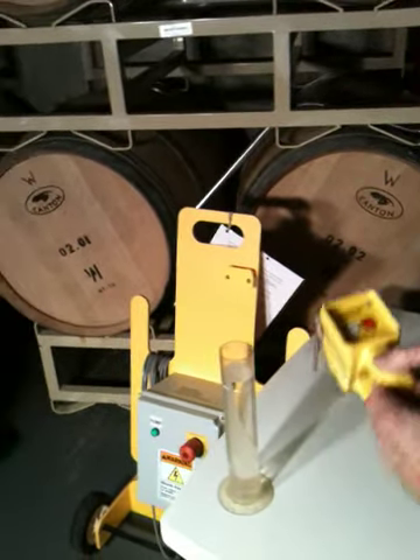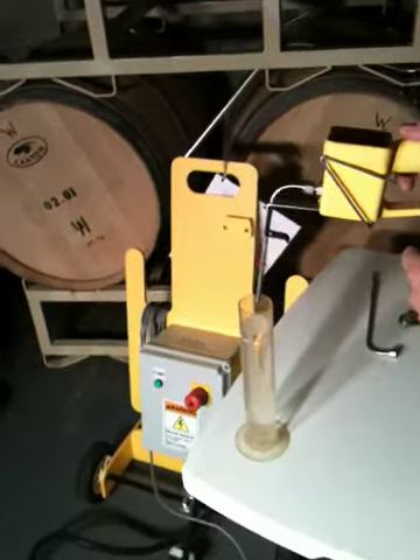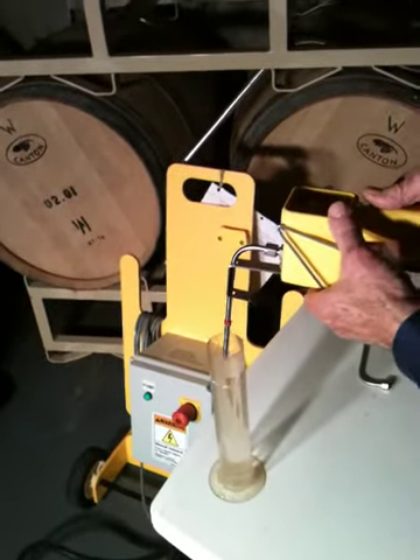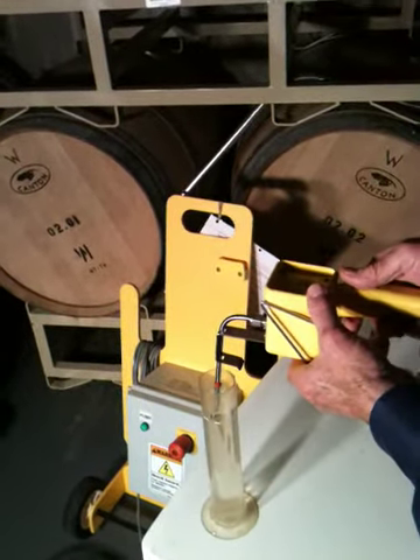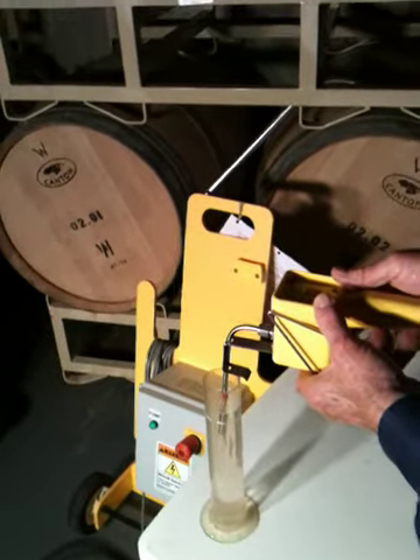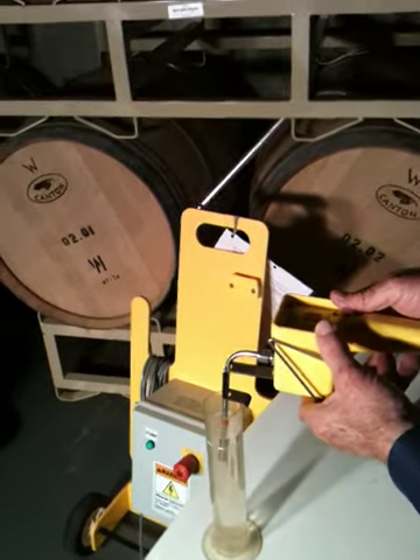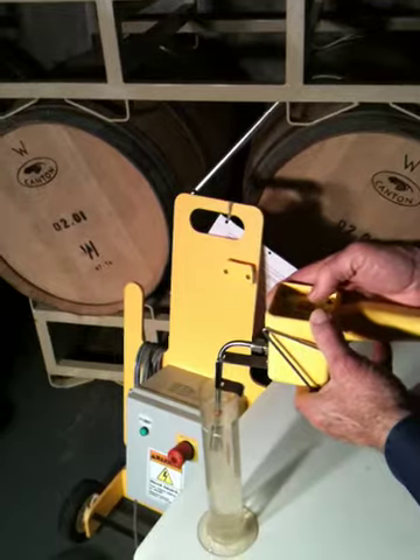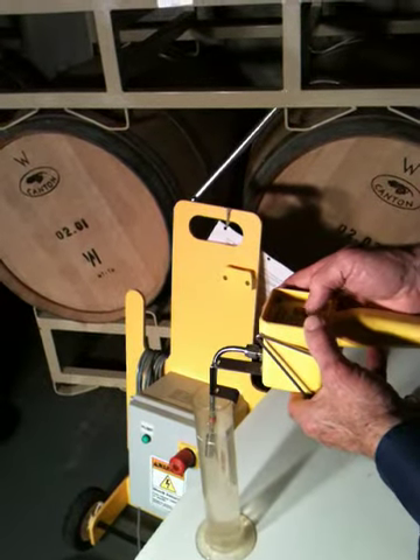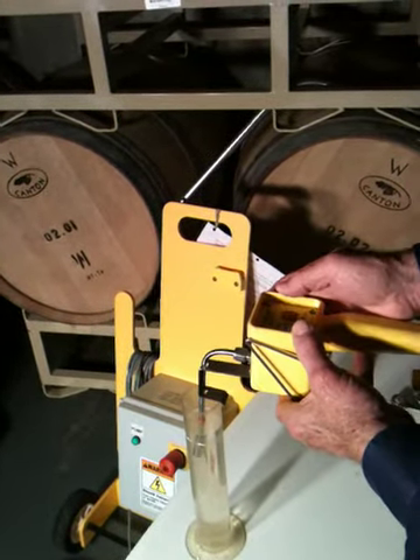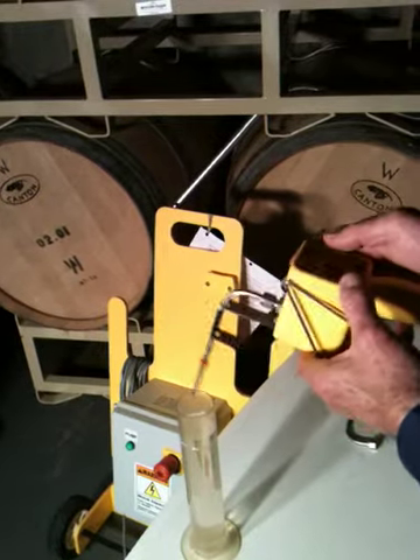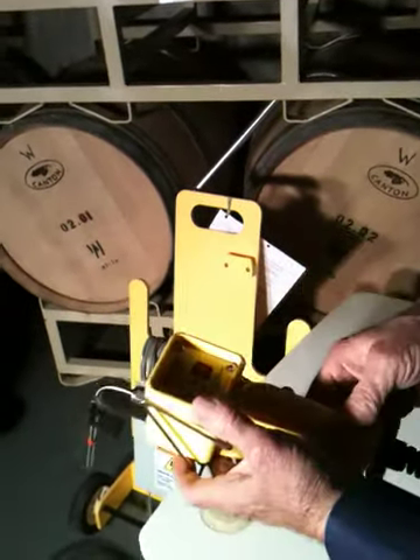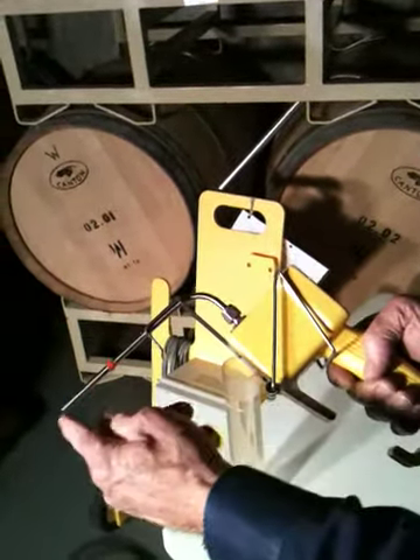So from the calibrate mode, we need to have a level of liquid in order to calibrate it on. So we're going to immerse the sensor down inside this liquid container. This is like a graduated cylinder. You could use a lab cylinder. And as soon as it reaches the red band, you hit the stop button, and that sets the level. Okay, so now it should be calibrated to operate on and off. When the level reaches this red band, it should cut off again.